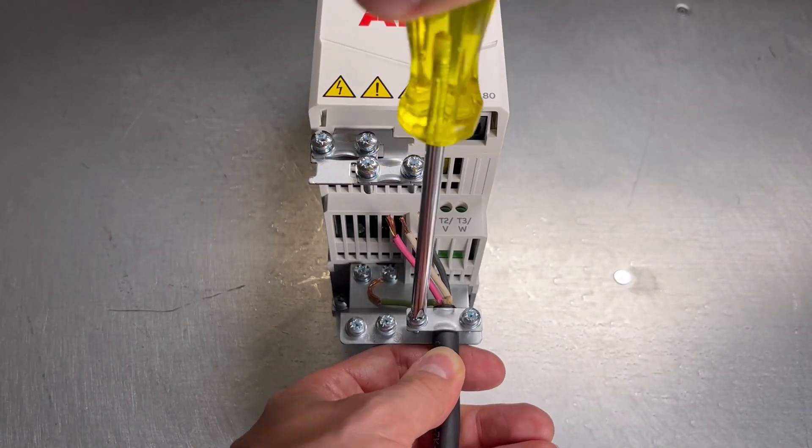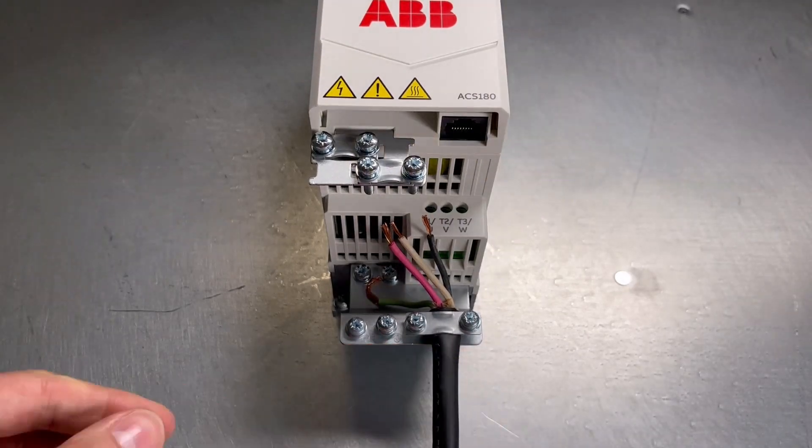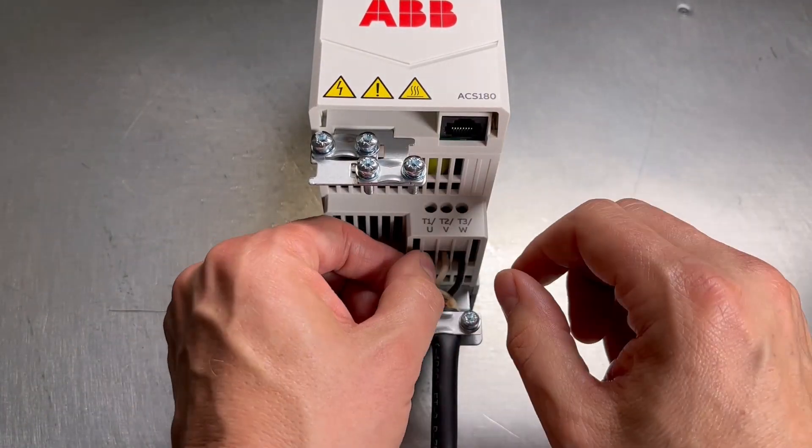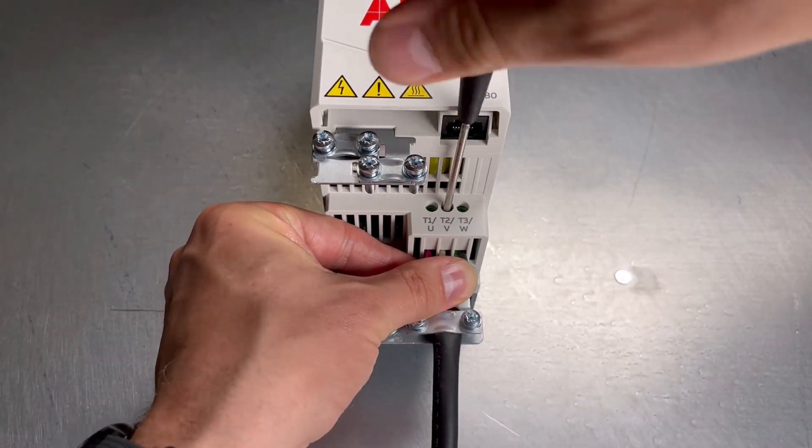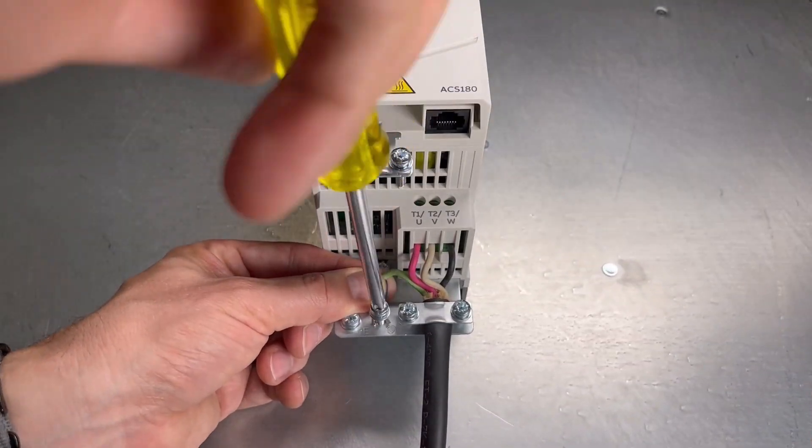Connect the phase conductors of the motor cable to the T1, T2, T3 slash UVW motor terminals. Torque the terminals to 0.8 Nm.